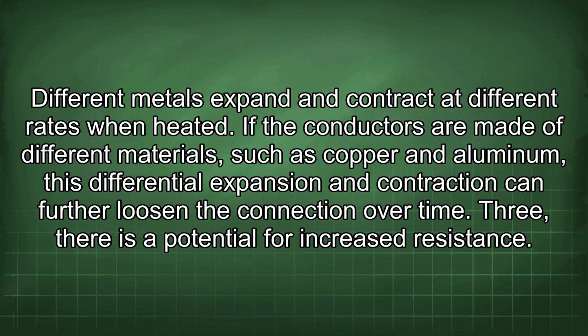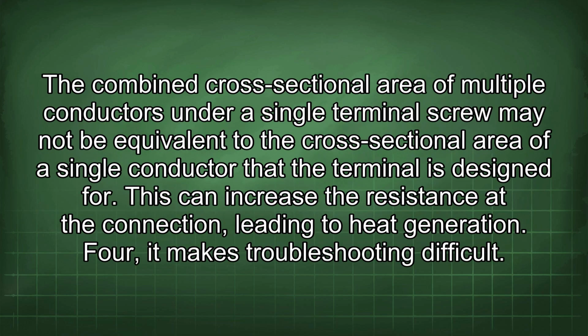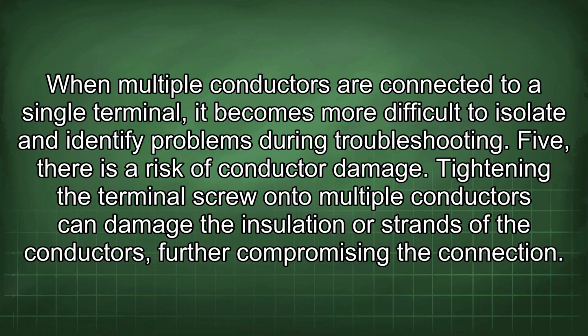3. There is a potential for increased resistance. The combined cross-sectional area of multiple conductors under a single terminal screw may not be equivalent to the cross-sectional area of a single conductor that the terminal is designed for. This can increase the resistance at the connection, leading to heat generation. 4. It makes troubleshooting difficult. When multiple conductors are connected to a single terminal, it becomes more difficult to isolate and identify problems during troubleshooting. 5. There is a risk of conductor damage. Tightening the terminal screw onto multiple conductors can damage the insulation or strands of the conductors, further compromising the connection.